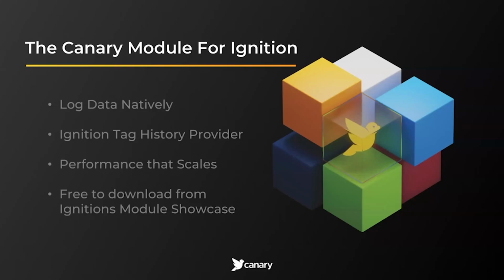And I did put a link into the chat that is focused on our Ignition module. If you are using Ignition for your SCADA system, we seamlessly integrate free of charge into their system. And the latest tested and supported version of Ignition is 8.1.43. And I will point out that the Ignition module by Canary and Inductive Automation can be used to both write data from Ignition 8 projects to the Canary system, as well as read historic and last known values from the Canary system and publish them to Ignition 8 projects.